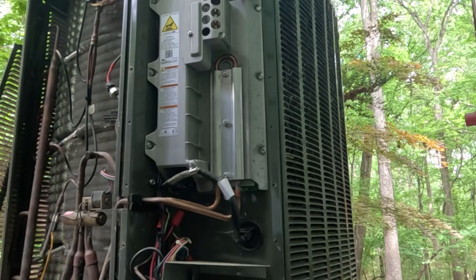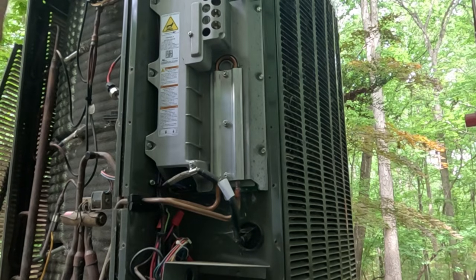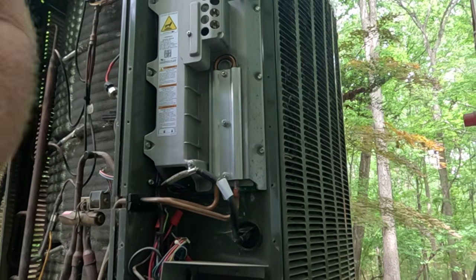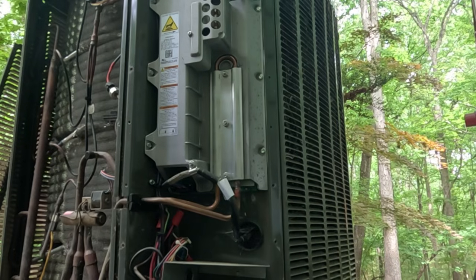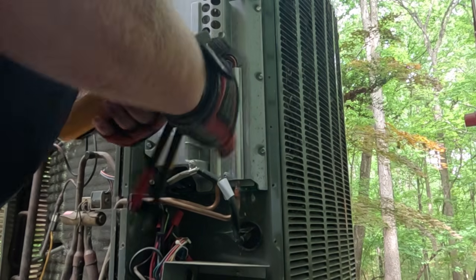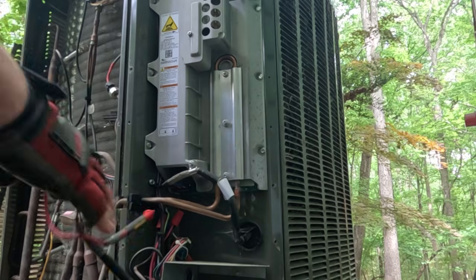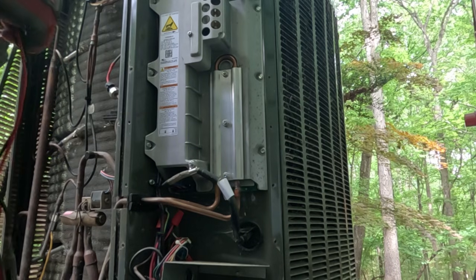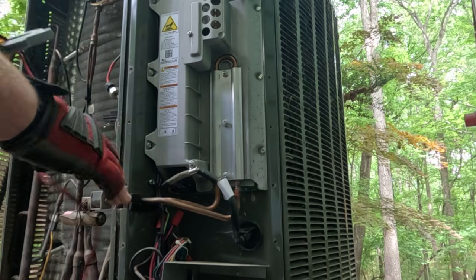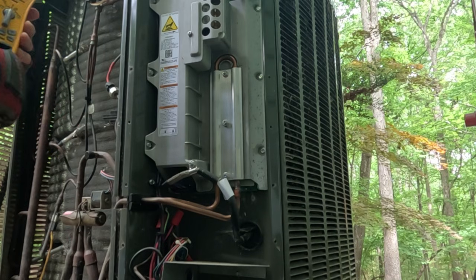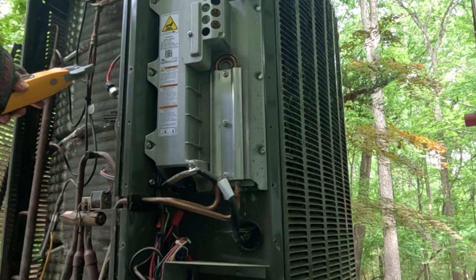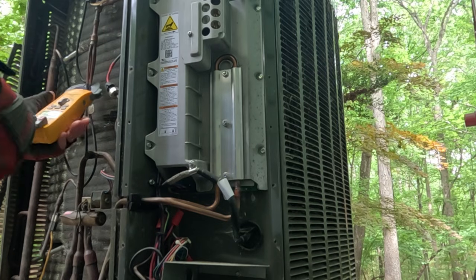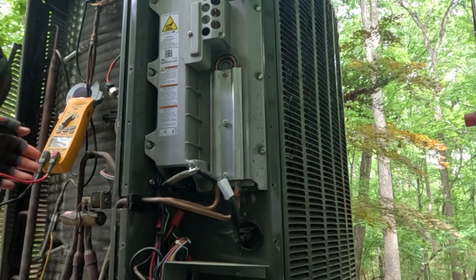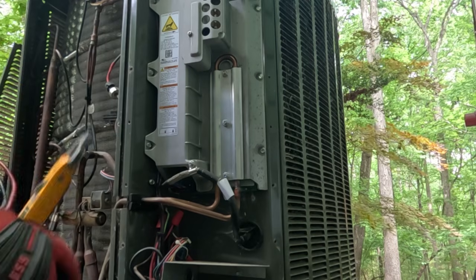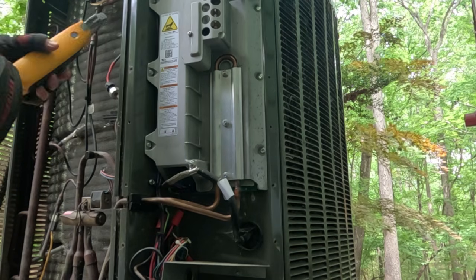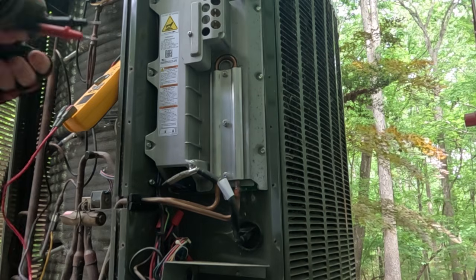I tend to want to put gauges on these because these sensors are just not trustworthy, and I've found the pressure transducers to be a little inaccurate. So I'm just old school. I'm gonna throw something on it, and I know my meters and my gauges and my sensors are all working properly, so I'm going to use the equipment I trust, not so much the equipment that tends to have a lot of issues.